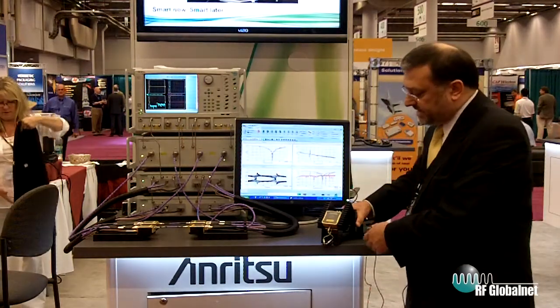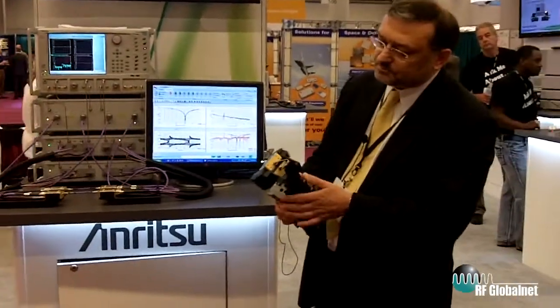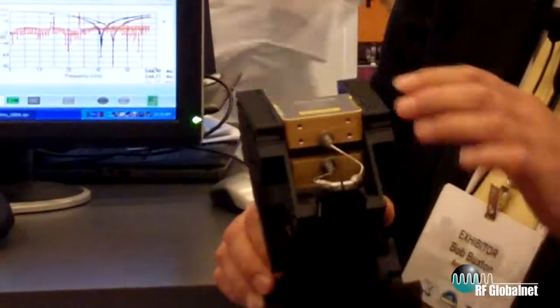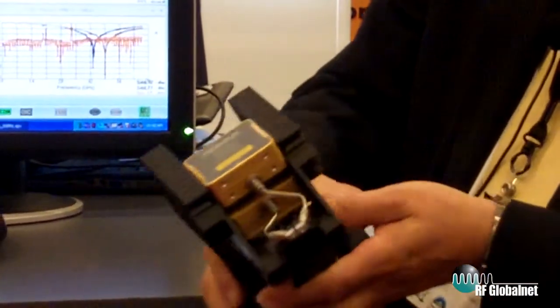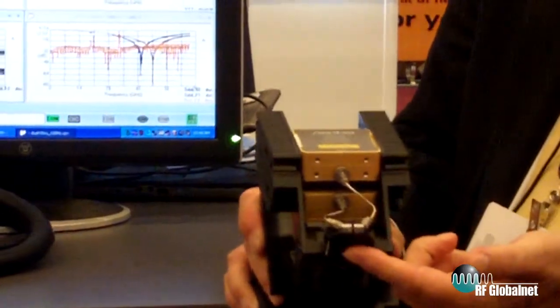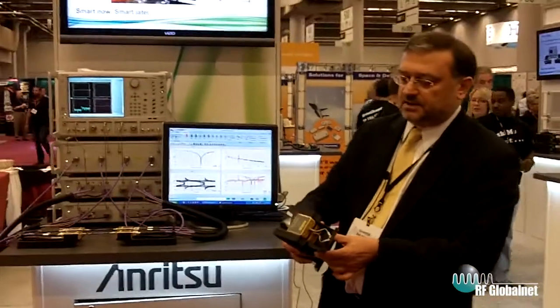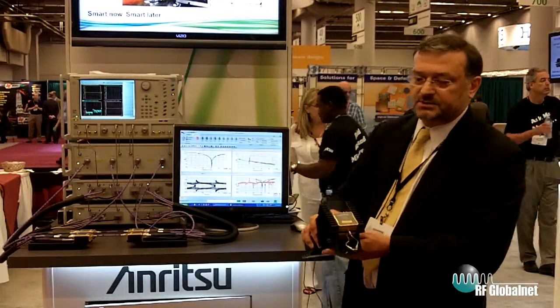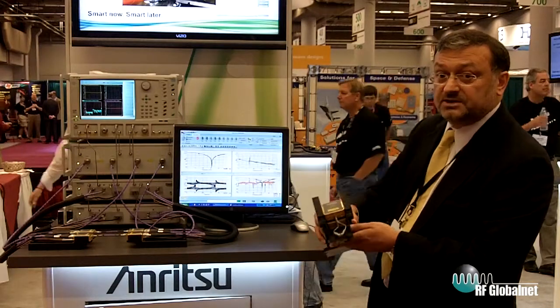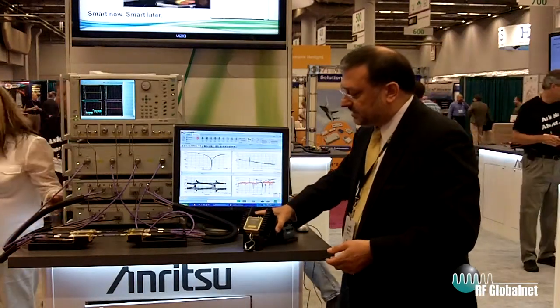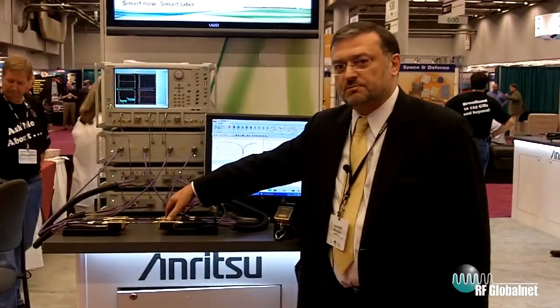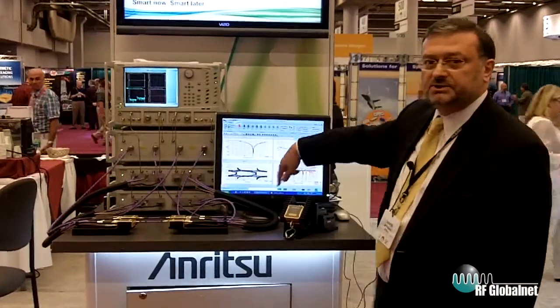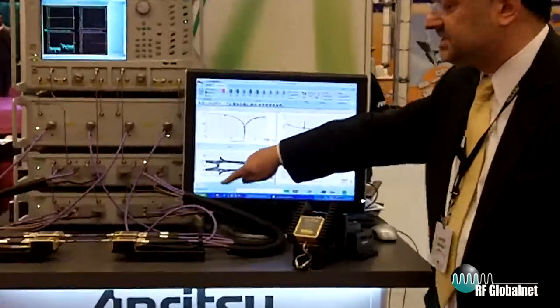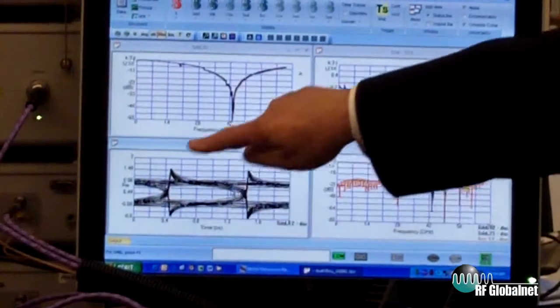4-port though isn't just used on the bench, it is used in on-wafer measurements, and here's an assembly showing how our modules mount together on a positioner for use with a probe station. And these are 2 modules connected to a differential probe. So again, providing much easier connection, mounting, and use of probe stations for people doing on-wafer differential measurements. Lastly, the use of 4-port devices is also important to signal integrity. So as part of this demonstration that we have here, we're looking at the predicted eye pattern on the screen here, based on the S parameter measurements made on these 2 lines.